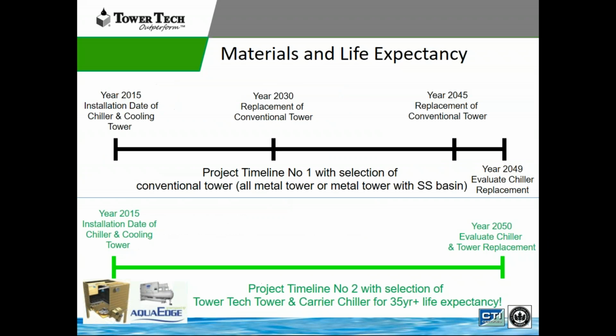When our tower is installed, typically it's installed with a chiller. On retrofits, it's not, but on a new application, you expect that chiller plant to last 30 plus years if you can get it. I know ASHRAE says 22, but you'd love it to last 35 years. So our cooling tower and our chiller are meant for that same lifespan, versus installing a traditional tower and then doing a major retrofit on that cooling tower maybe 15 or 20 years into its life. So we're eliminating that piece of it. Now, you may have to replace the fill in that time period, obviously, but not the structure of the cooling tower.